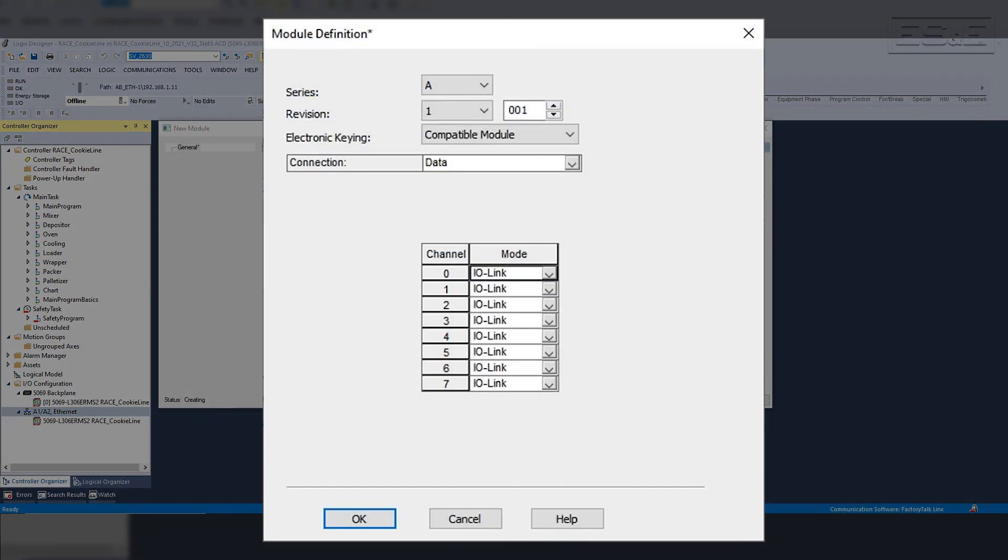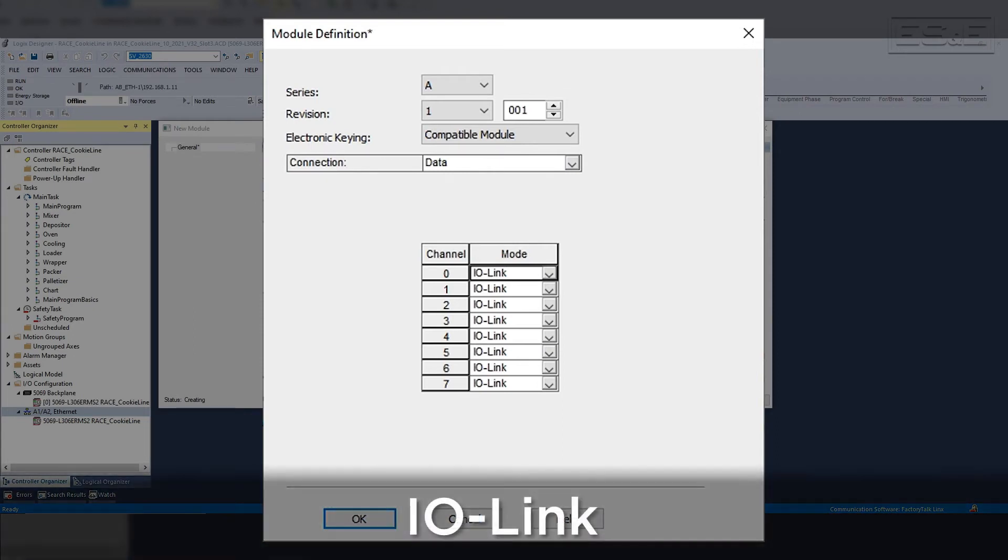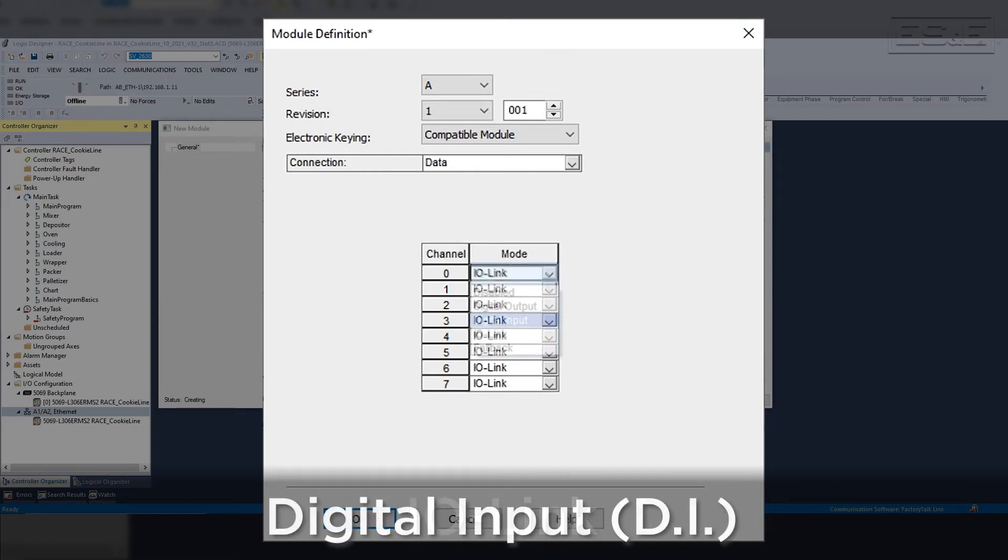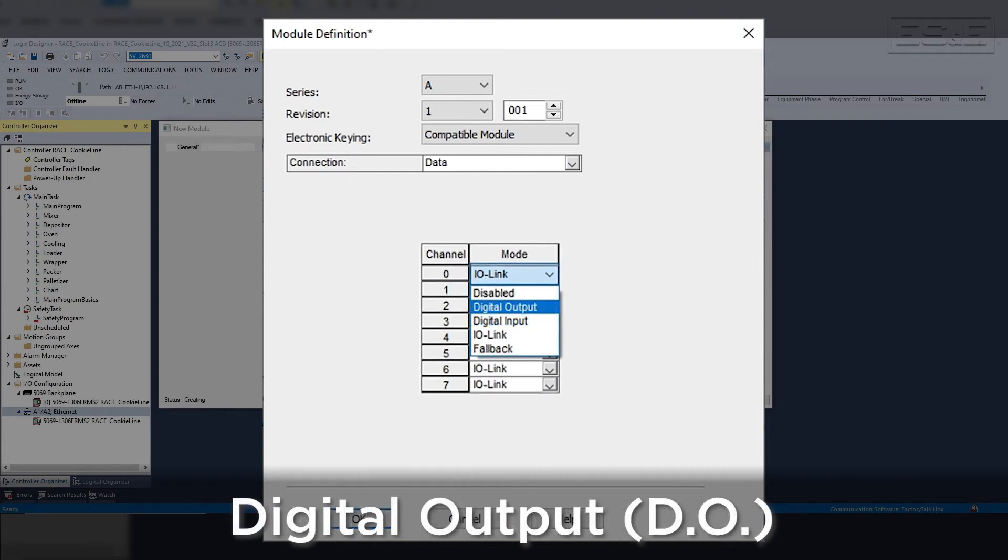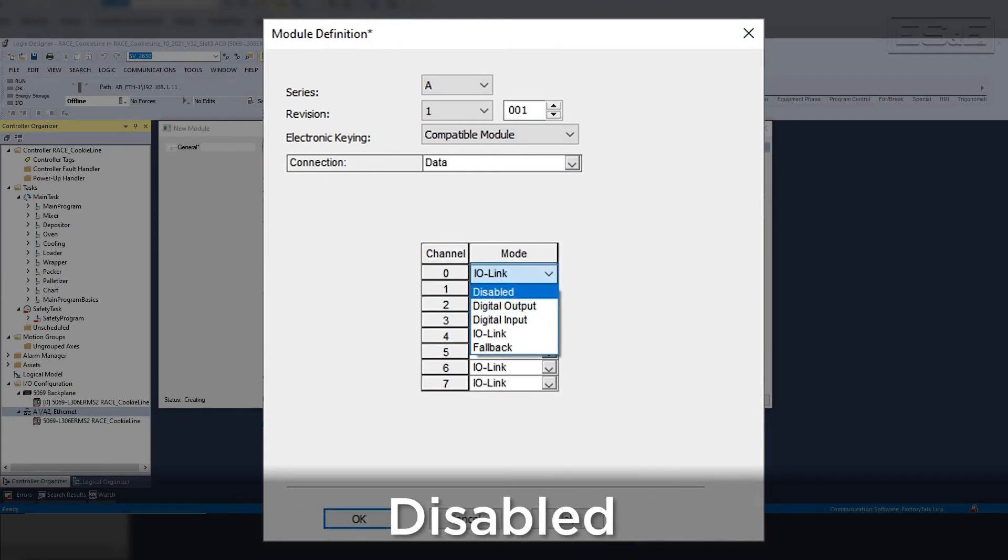Rockwell IO-Link Masters can be configured in one of five different modes. The first mode is the IO-Link mode, which means that the port is used for IO-Link communications. The second mode is DI, which means the port acts the same as a standard digital input device. The third mode is DO, which means that the port acts the same as a standard digital output device. The fourth mode is disabled, which means the port is not assigned to any mode.